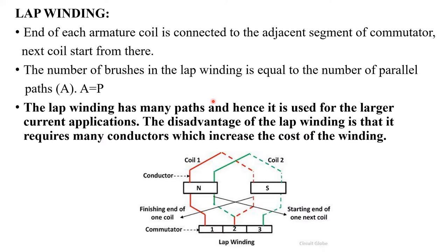Let us discuss about lap windings. In lap windings, the end of each coil will connect to the adjacent segment of the commutator, and the next coil will start from that commutator segment. Here you can see a red colored coil — it will start from commutator segment 1 and end at 2, and from that 2 the next coil starts.